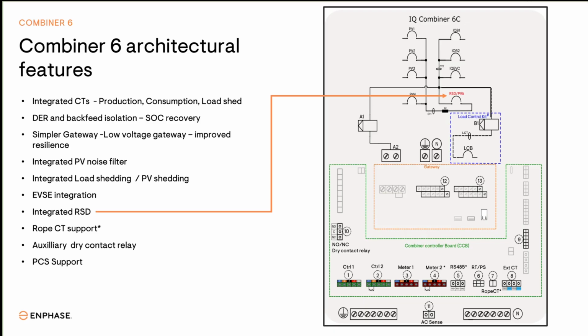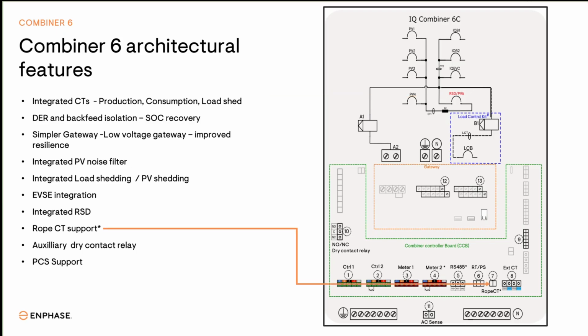The Combiner 6C has provision for rope CT connections when these are needed in difficult wiring situations. Another feature of the Combiner 6C is an auxiliary normally open or normally closed dry contact relay used as an option to control external loads. The normally open, normally closed control can actuate a custom load controller or even be connected in line with a thermostat line to control HVAC units. The contact can control up to a 120-volt, 1-amp load.